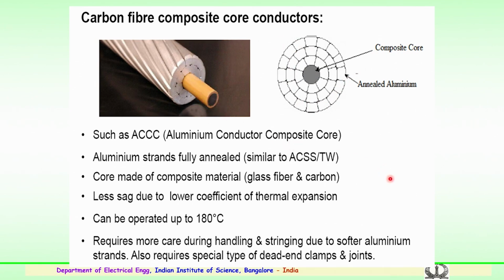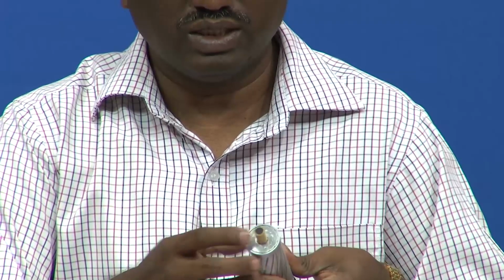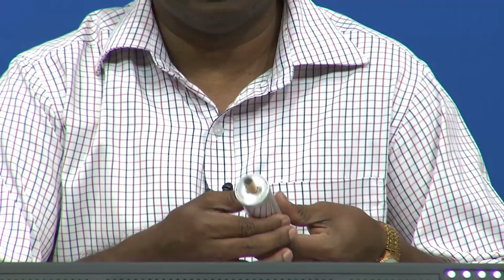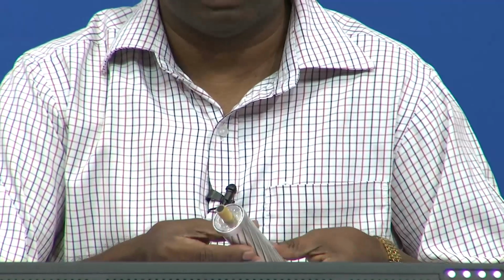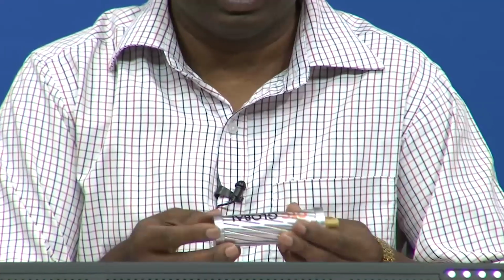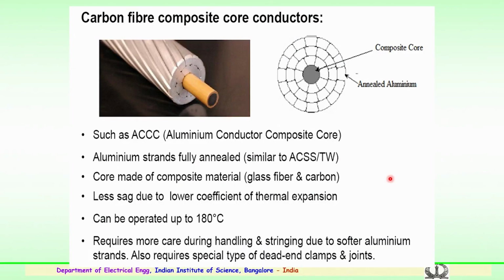A sample of the conductor is also shown here, where you can see the construction. There is no gap, particularly with the conductors which are connected at the tips, and this is the carbon core, the composite core, which replaces the steel core of the earlier conductors which we have discussed. So, this has special properties in comparison with the ACSR conductor. This ACCC, or aluminum conductor composite core, which is shown here, has aluminum strands fully annealed, similar to the previous two types of high temperature conductors, but the core is made up of composite material.